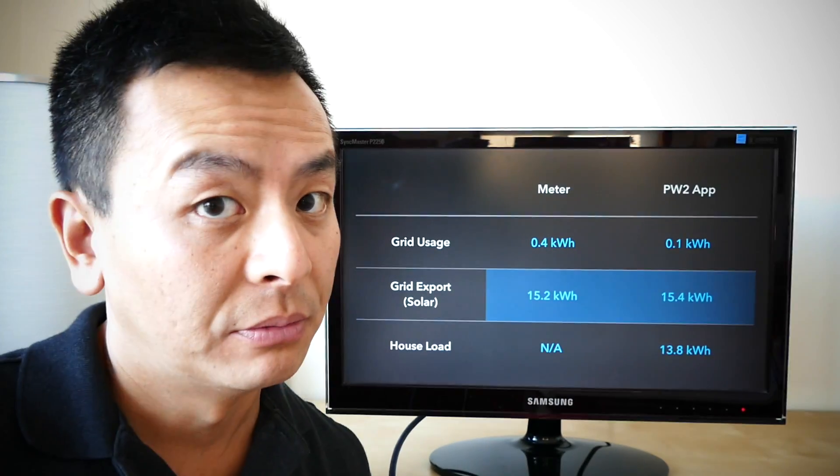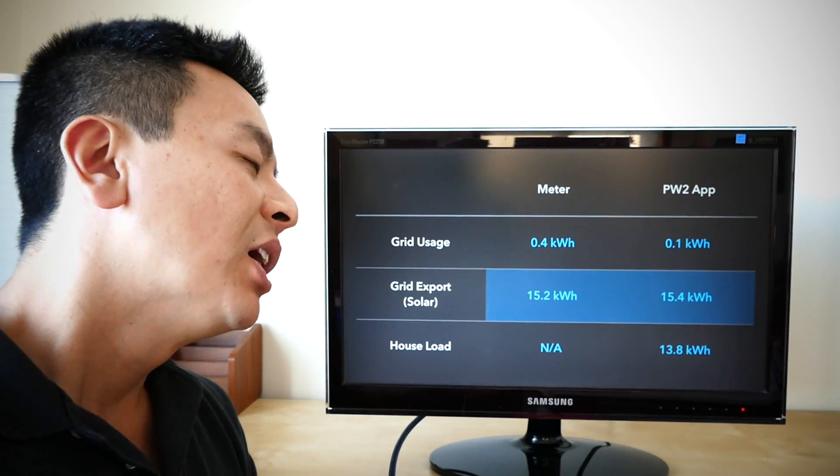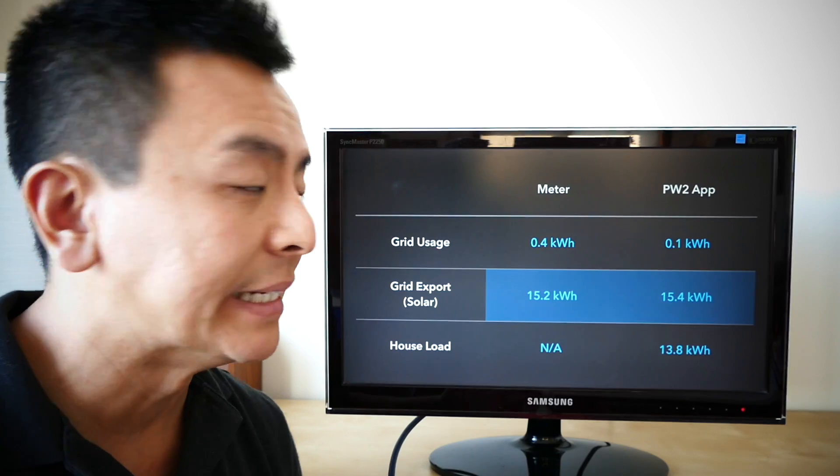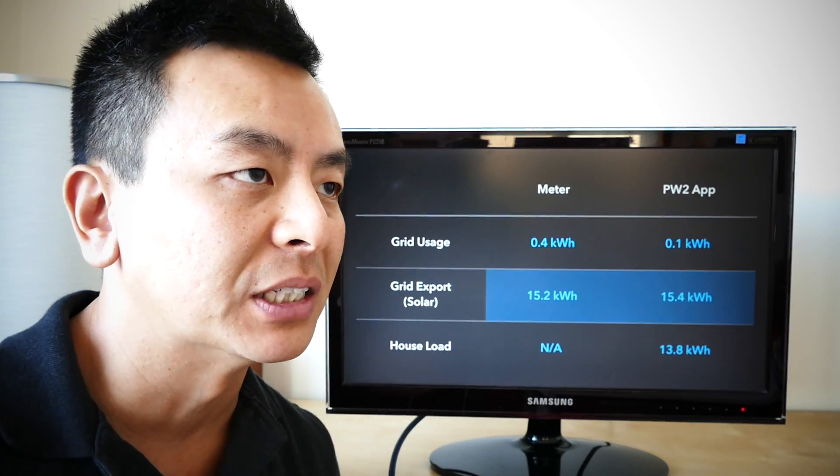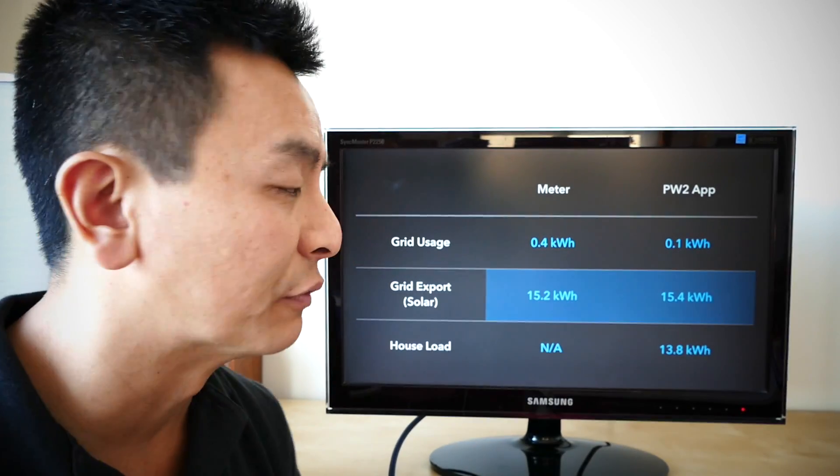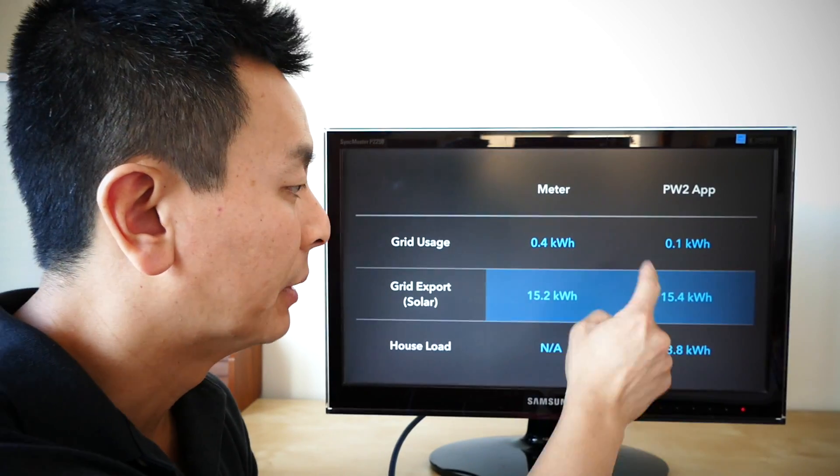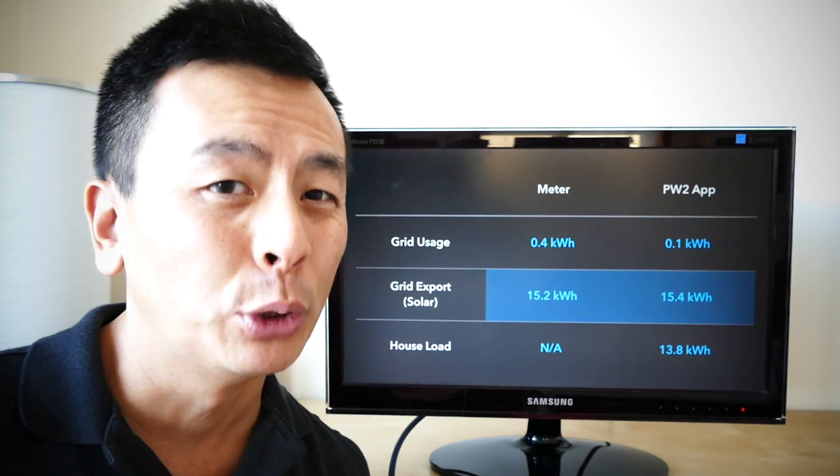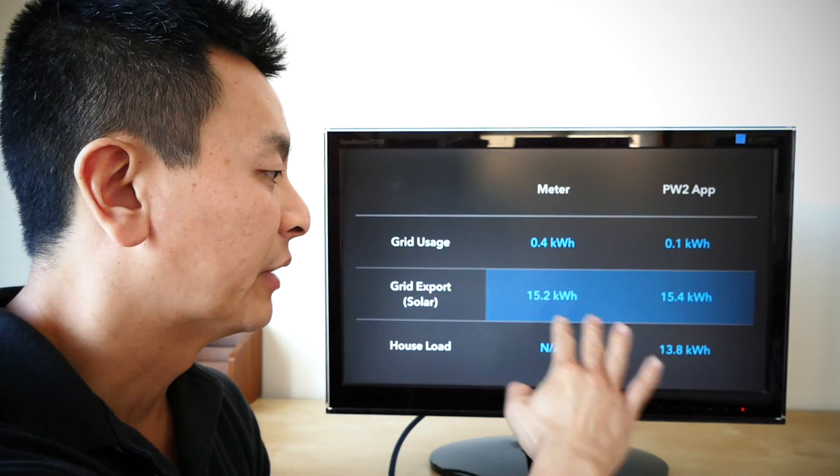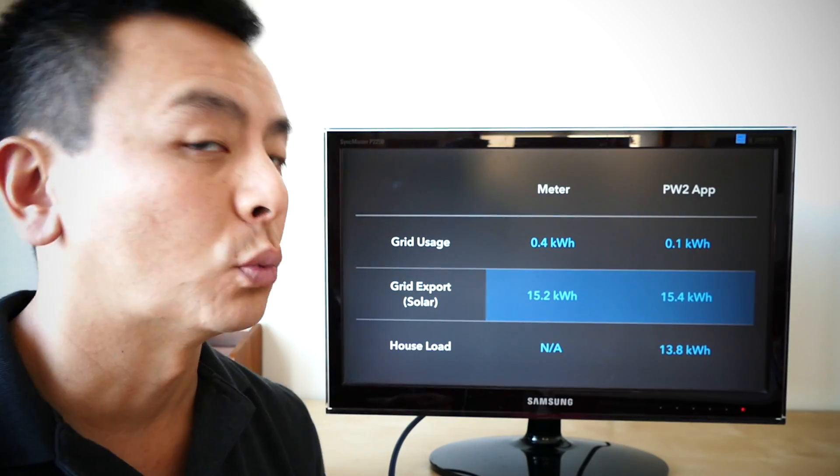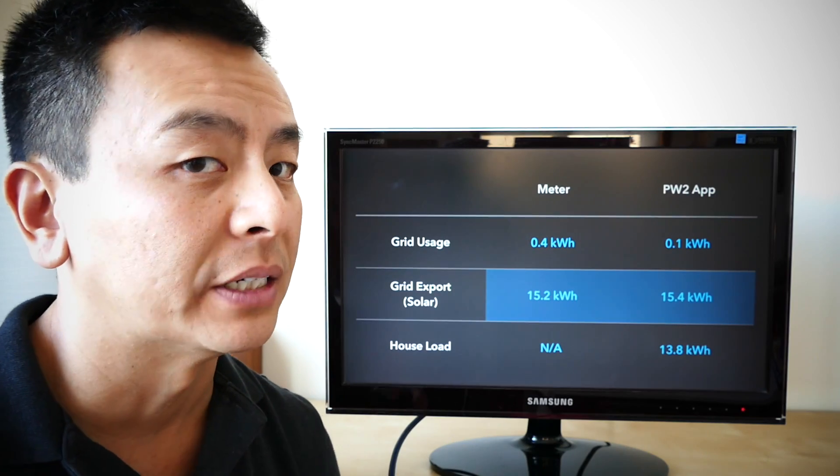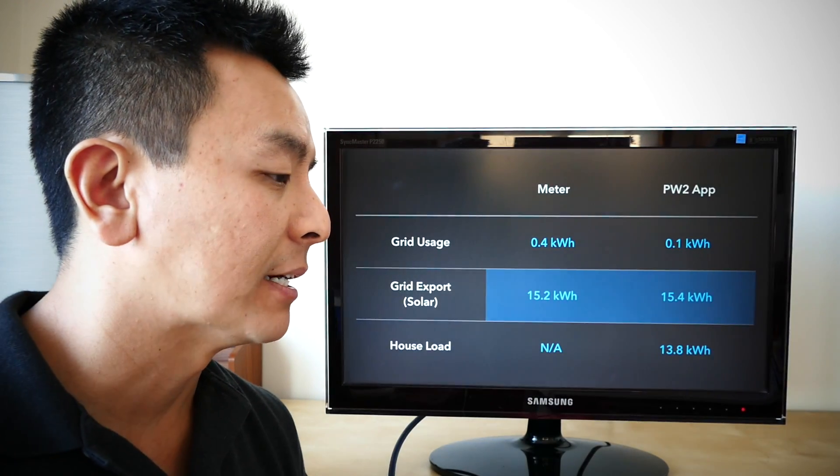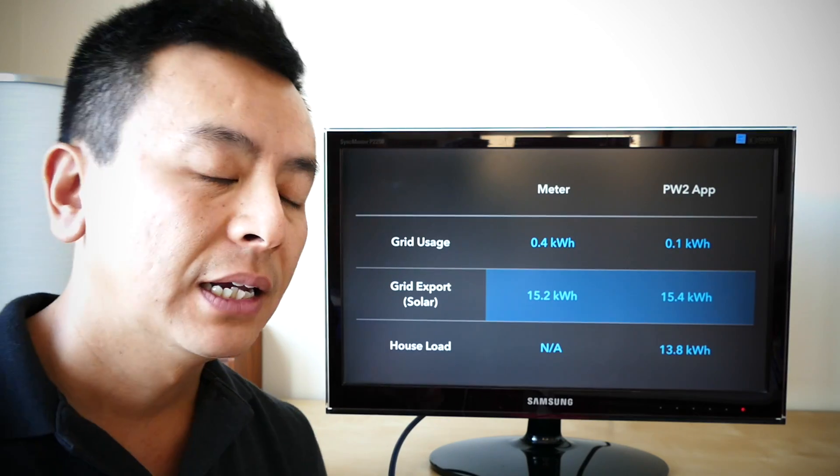So the question remains, is it accurate? Well, on the face of it, I would say yes. Sure, it's 0.3 kilowatt hours difference, but honestly, that's a very small difference. And if you look at the error rate when you compare it to the load, that's at about a 2% error rate or within the margin of error 2%. In terms of export, that margin is even less. That's close to 1%. So I'm happy to accept that 1 to 2% error rate. I can safely say that I can rely on my Powerwall 2 app on a day-to-day basis.